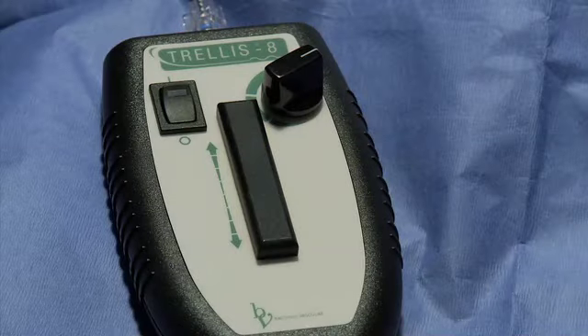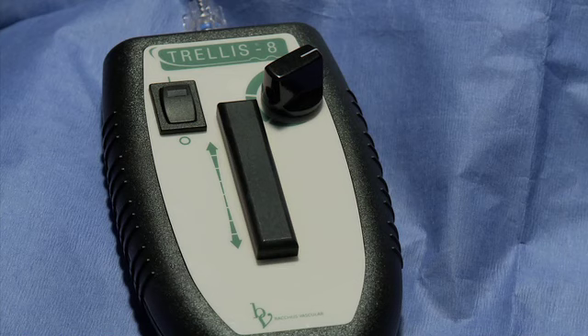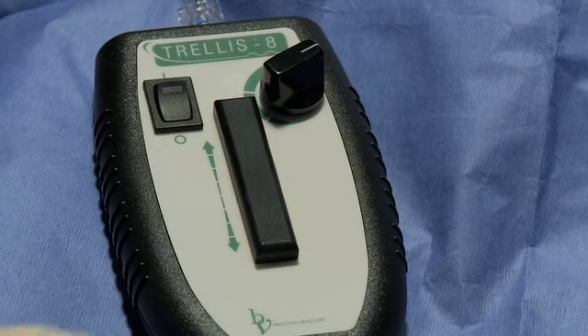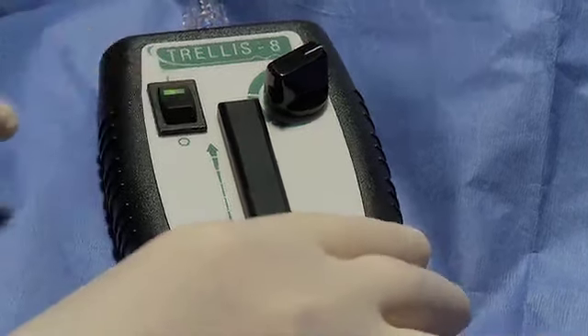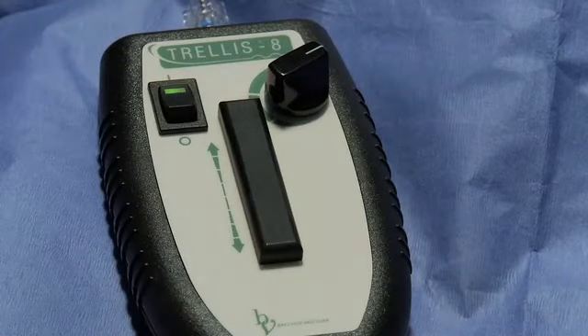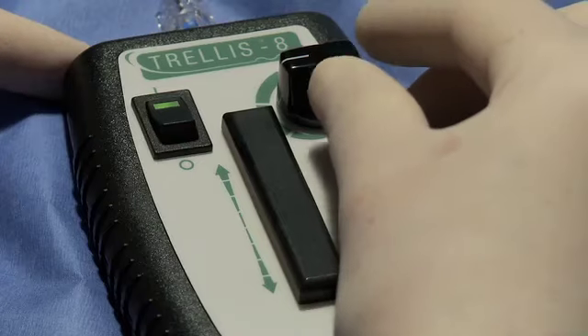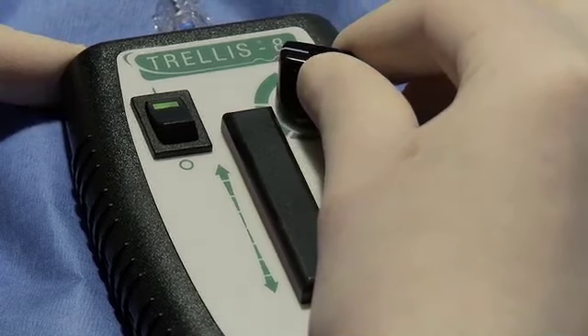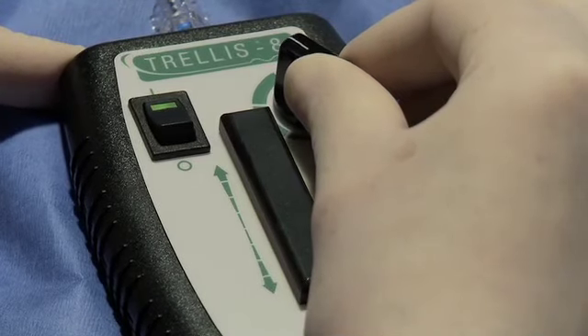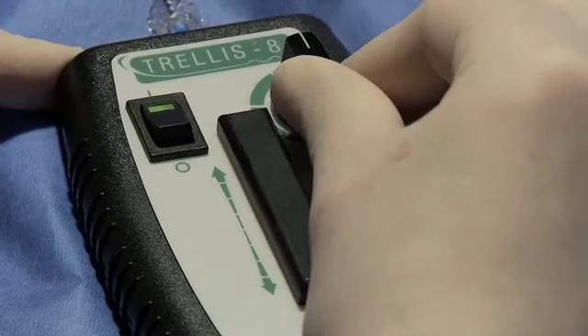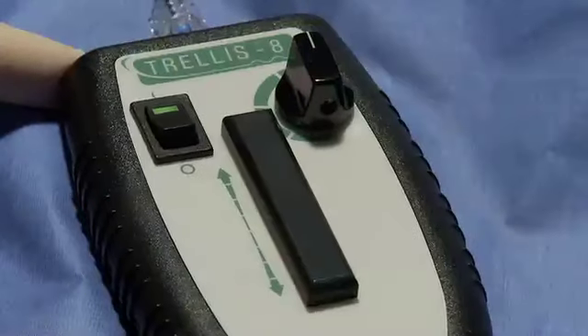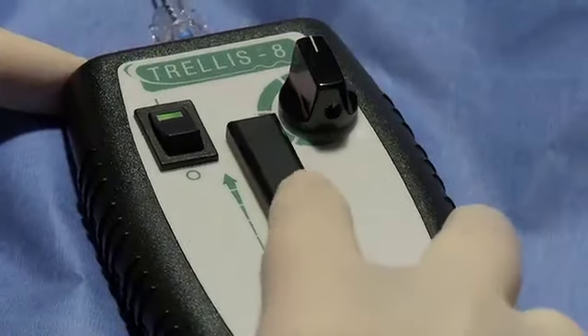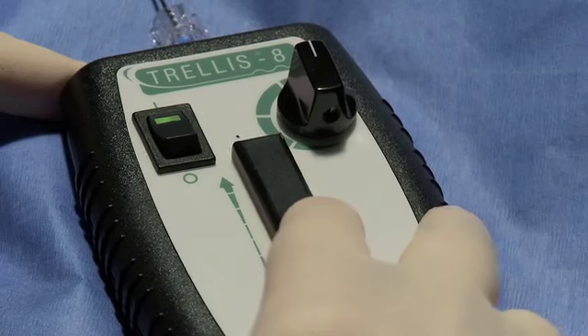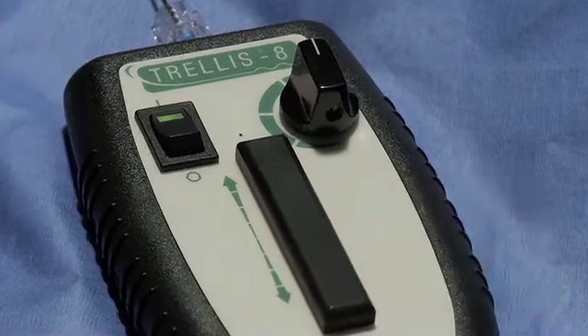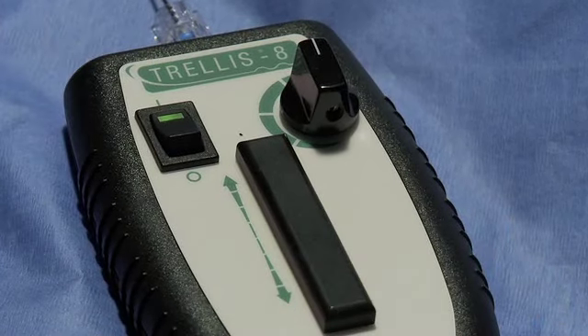The oscillation drive unit, or ODU, allows the user to turn on and off the device and control the speed and position of the oscillating dispersion wire. The speed control knob alters the speed of the oscillation, which can range between 500 and 3000 RPMs. The translation bar allows for repositioning of the oscillating dispersion wire during the procedure to enhance the amount of the surface area of thrombus that is exposed to physician-specified fluids.